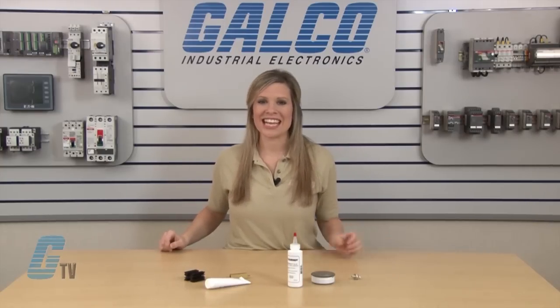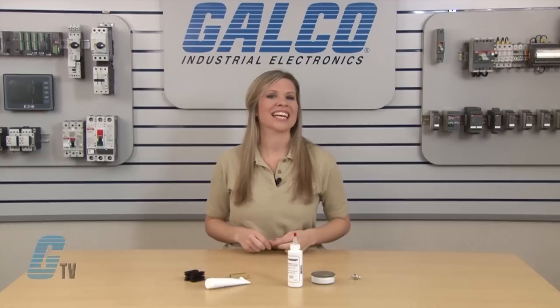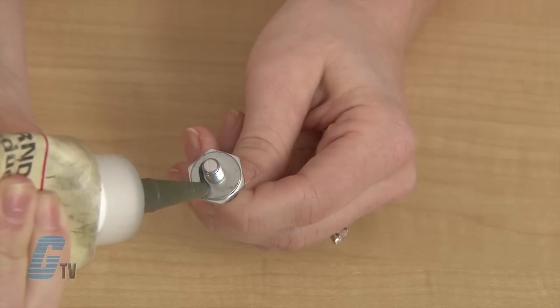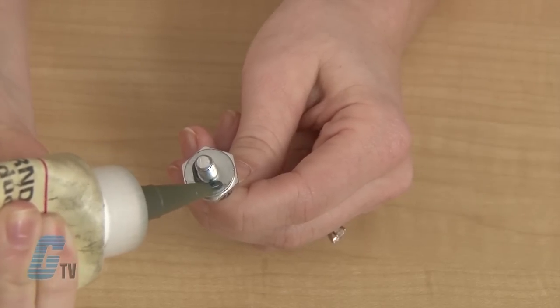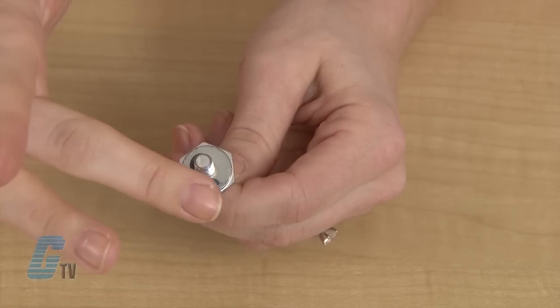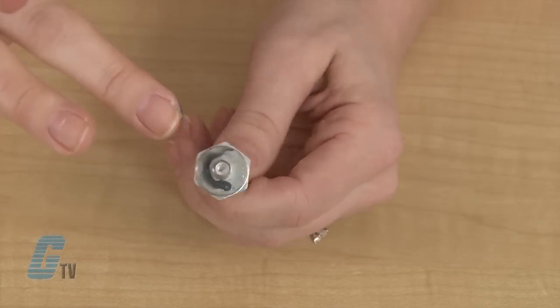The Penetrox A13 is non-petroleum based with suspended zinc particles and works well with aluminum to aluminum and aluminum to copper applications. This material is easier to clean and can be applied with a finger or brush. For stud mounted devices, this should be applied liberally to the base of the stud before applying to the heat sink.